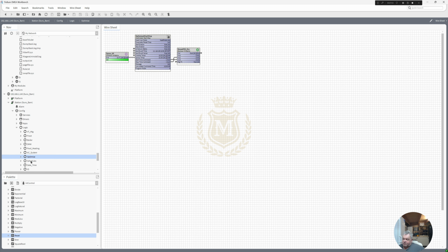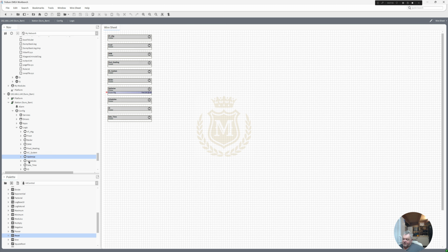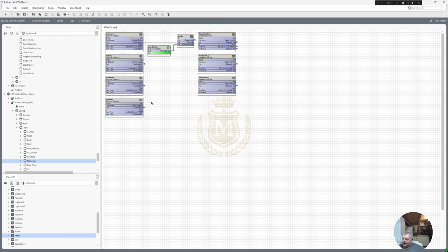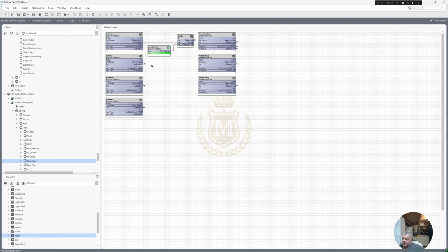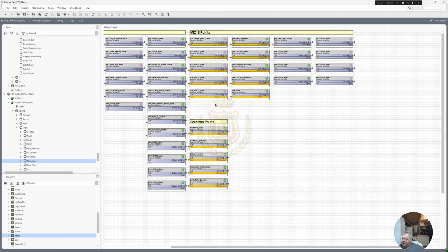The optimizer's not being used. All I'm doing there is taking that to there, but I'm not using it. The normal schedulers here. Now we've got a generator, and they wanted a generator switch, so naturally the scheduler comes on a Monday, 10:35 to 10:36, so it's 1 minute. That's what they asked for, but they've got a switch that they can switch it on themselves, and that takes us to the generator enable there, start signal.